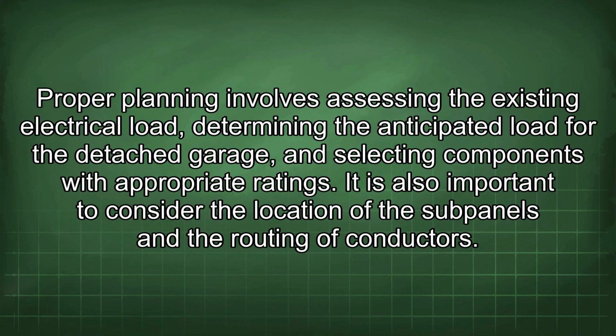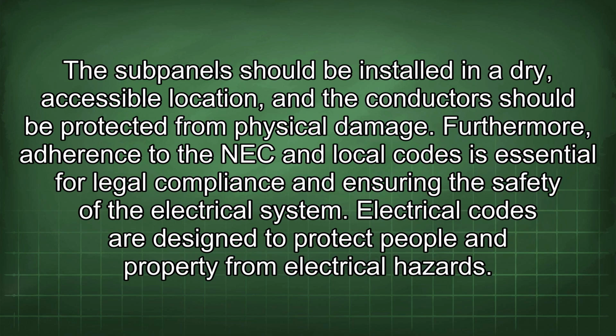Proper planning involves assessing the existing electrical load, determining the anticipated load for the detached garage, and selecting components with appropriate ratings. It is also important to consider the location of the subpanels and the routing of conductors. The subpanel should be installed in a dry, accessible location, and the conductor should be protected from physical damage.